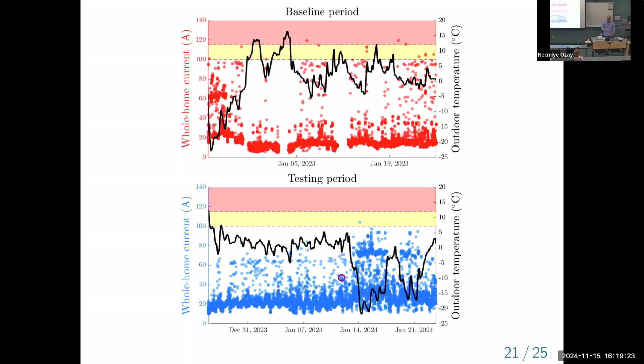We fixed it by updating the control logic to look ahead further and make better predictions of when people are going to take showers, so we can preheat the water tank to have plenty of capacity through the early morning periods, which is when this happened. I don't know if that's justification for needing all the complicated machinery of predictive control, but it certainly means you need some anticipative logic in the control system.